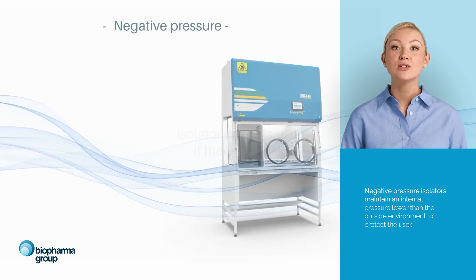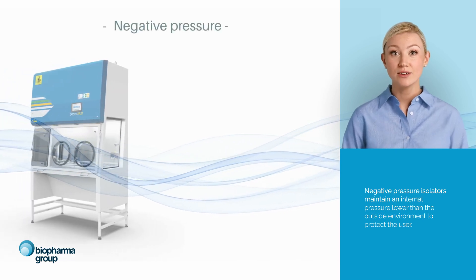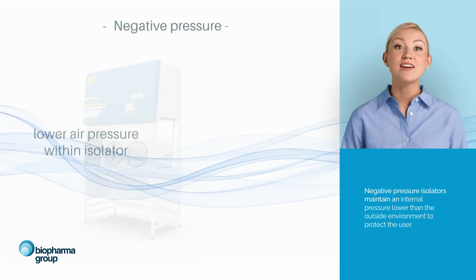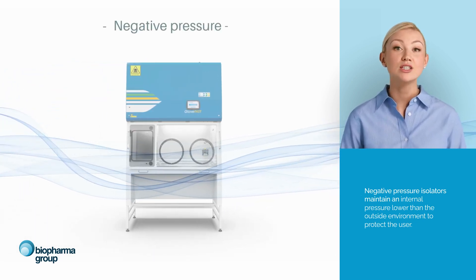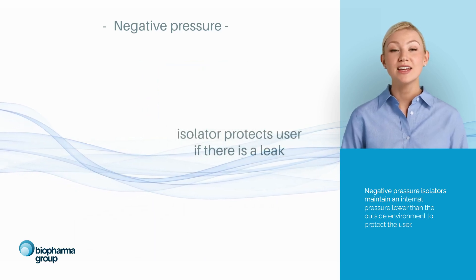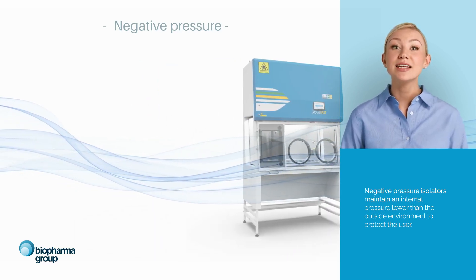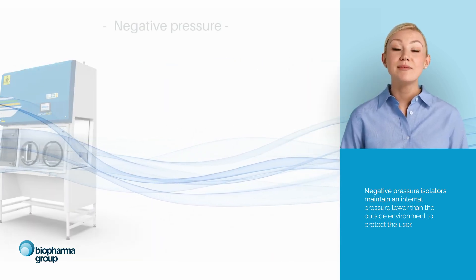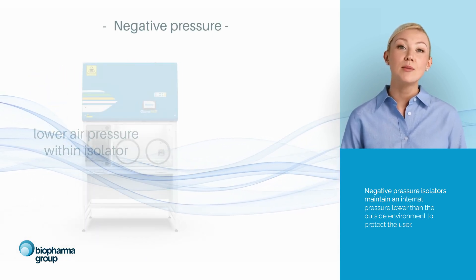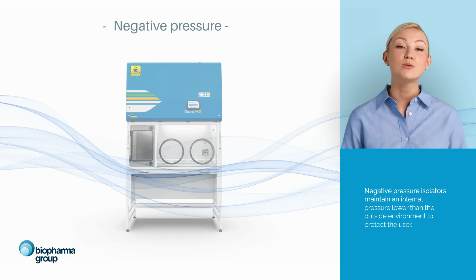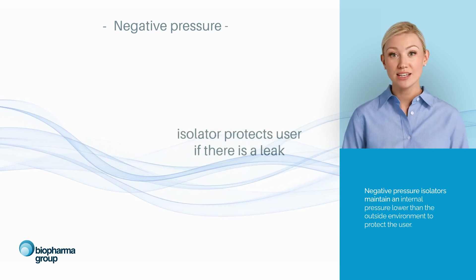For cytotoxic handling, negative pressure operation is generally favored because in the event of a leak developing, cytotoxic drugs will still be contained within the isolator. These are especially suitable for applications such as cytotoxic and CMR preparations or small production of cytotoxic or toxic drugs.